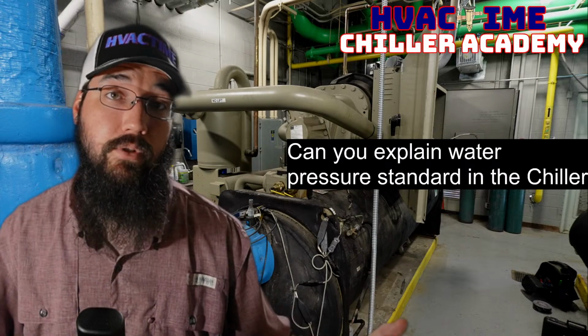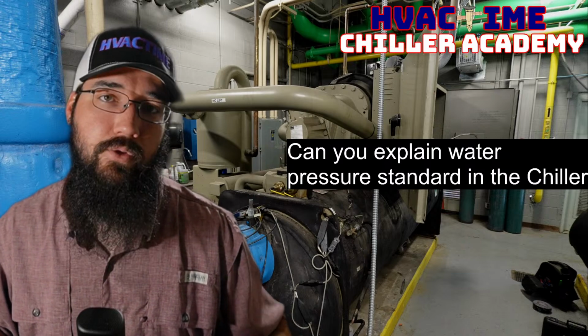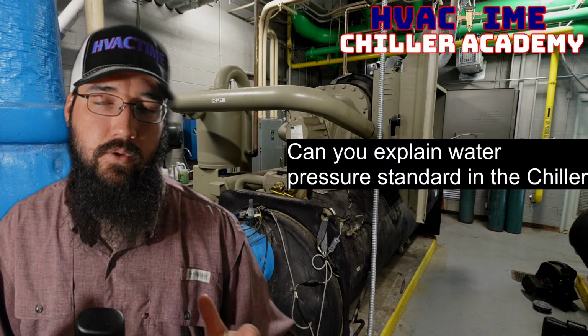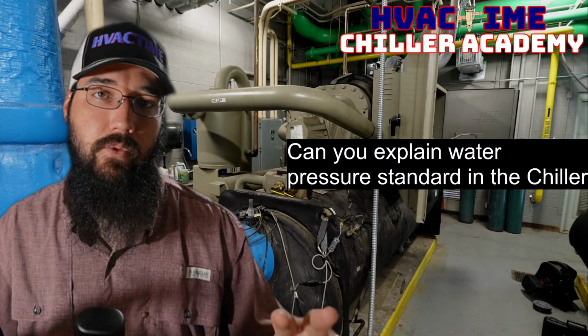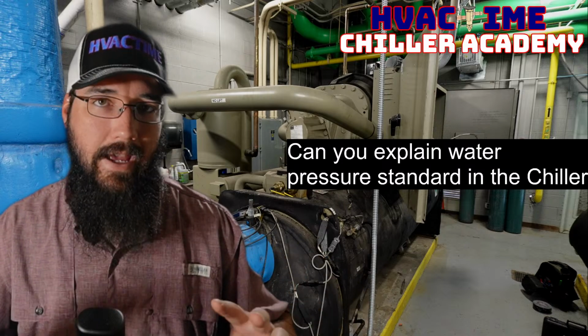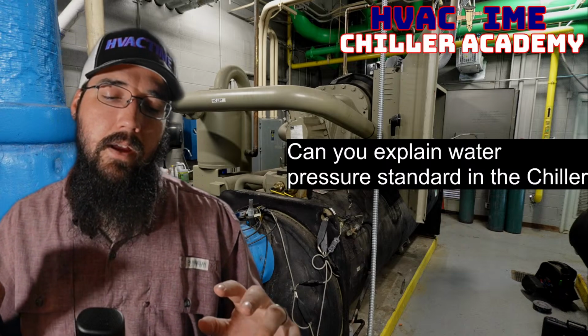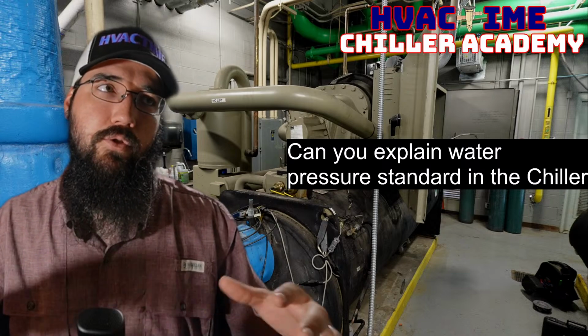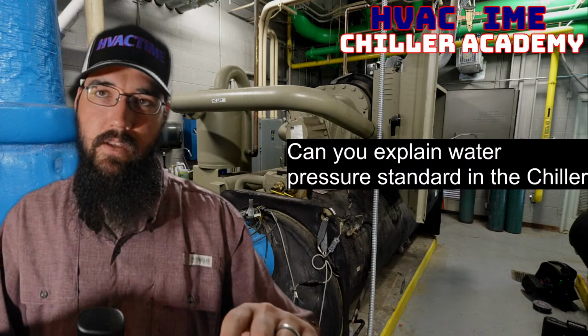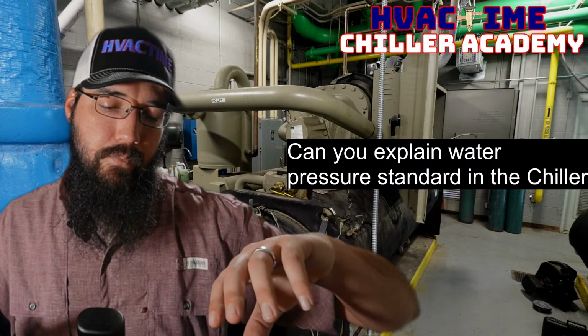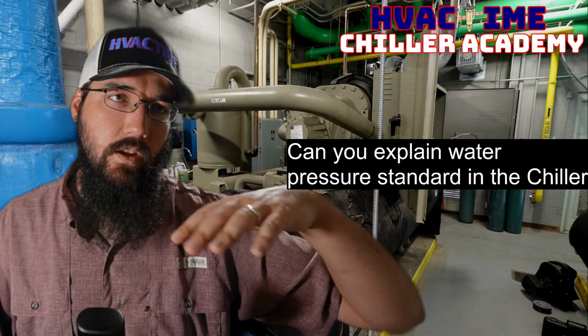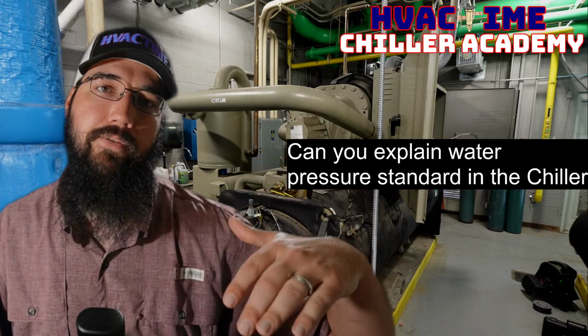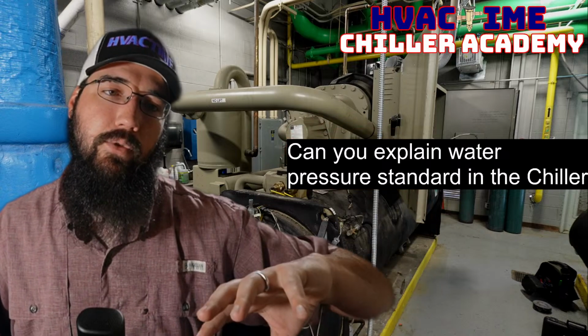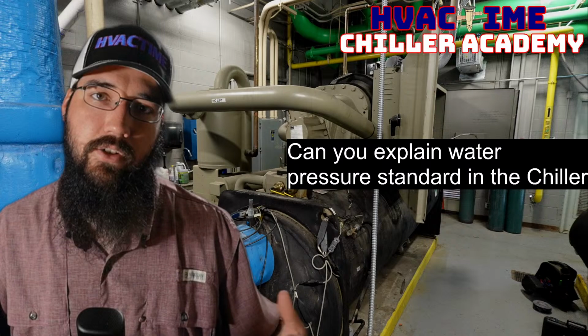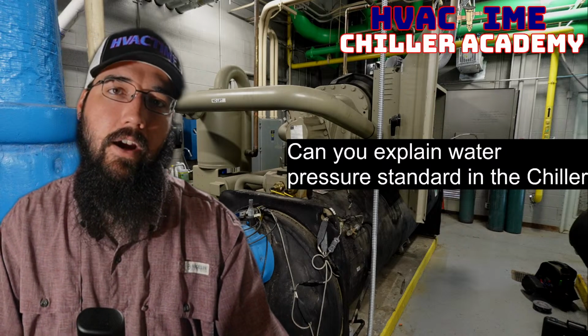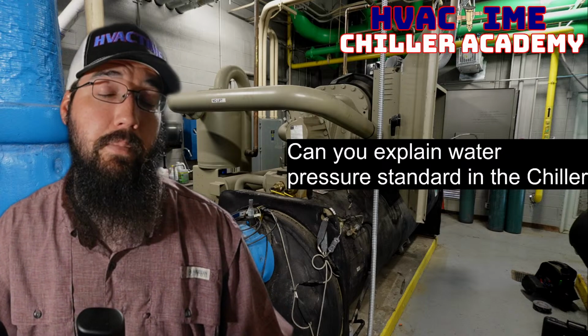If you're trying to go from just a loop pressure perspective, that comes back to your actual elevation. Now, there are going to be some special circumstances where they have higher pressures than what your normal calculation would be for that application, okay? That becomes very specific. But in most of your general purpose plants, I'm going to say it that way, so it could be used on a variety of things, that's going to be based off your elevation. So we want to make sure that at the top of our loop, we are full of water with a little extra headroom. And if we make sure that we have enough water, then we're not going to have issues with cavitation and things at the pumps, which is, literally air being pulled apart and separated from the water, which then creates air pockets without actually having a leak, right?